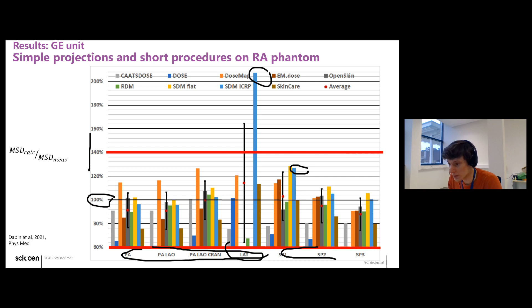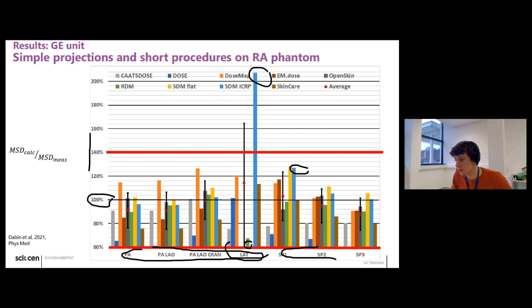And it's difficult to say much more than that. You can see, for instance, that some software tools, like these 2 here, usually give results close to each other. And the really obvious observation here is for lateral projection, when the beam is at 90 degrees, not under the table but lateral to the patient: the results are really poor or can be really poor. You can see here an overestimation of more than 100%. Underestimation you don't see, but it can go down to 66%, and some software tools don't even give an estimate of the skin dose when it's a lateral projection.